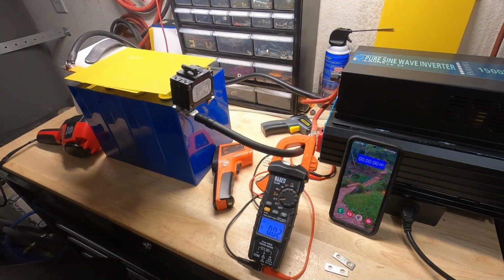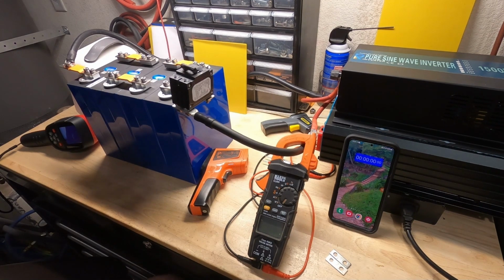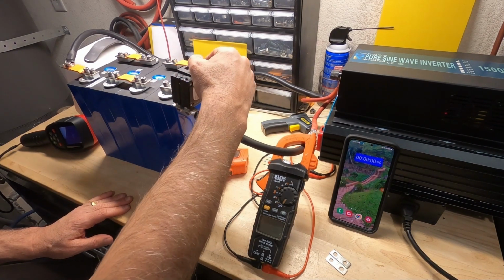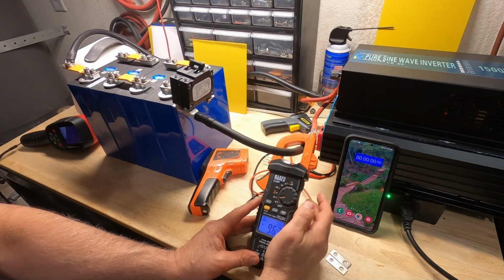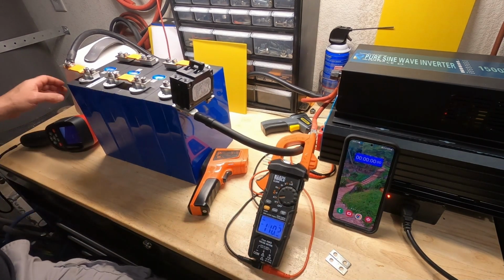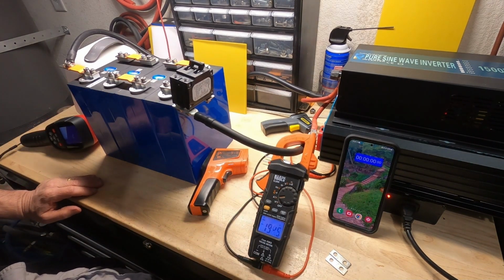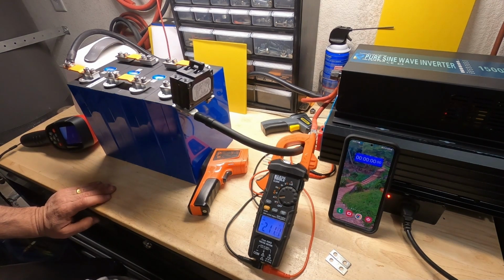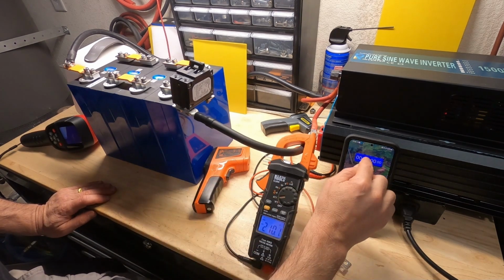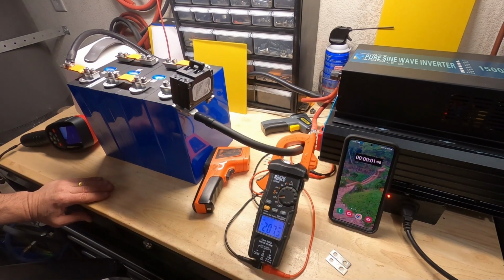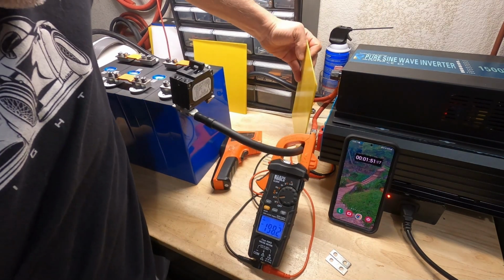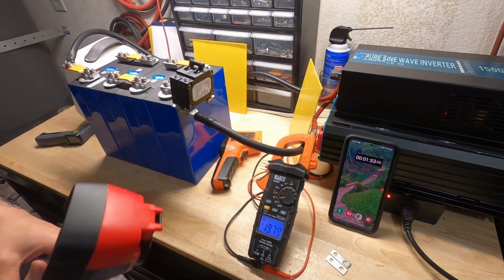Okay, here we go. Modified setup with copper bus bars. Let's hit it with 200 amps. Here we go. 211 amps. Start our timer. The first check-in will be at 2 minutes. Can't have the fan in the way. We're approaching 2 minutes.